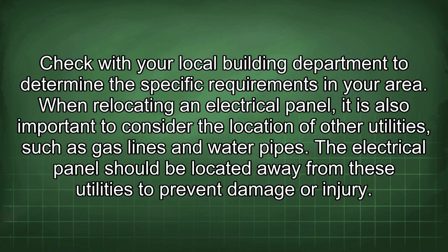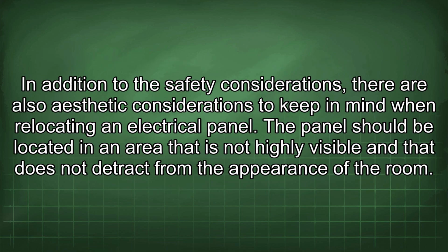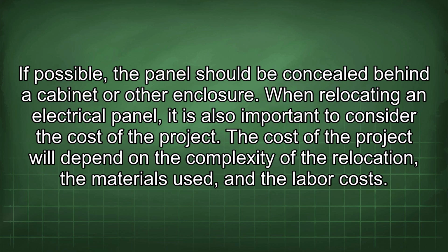When relocating an electrical panel, it is also important to consider the location of other utilities such as gas lines and water pipes. The electrical panel should be located away from these utilities to prevent damage or injury. In addition to the safety considerations, there are also aesthetic considerations to keep in mind when relocating an electrical panel. The panel should be located in an area that is not highly visible and that does not detract from the appearance of the room. If possible, the panel should be concealed behind a cabinet or other enclosure.